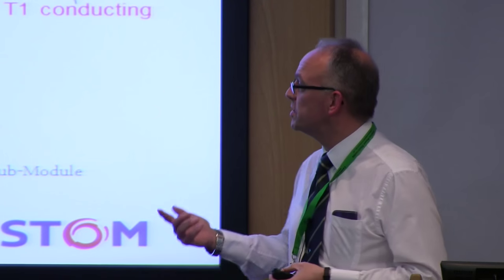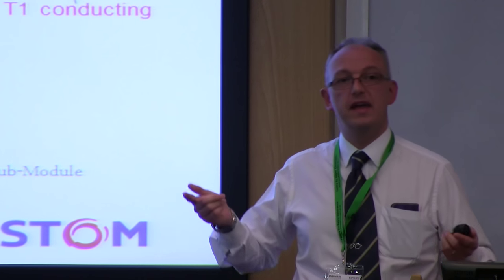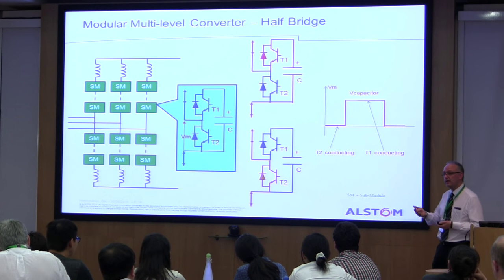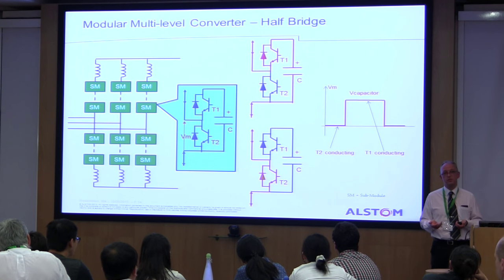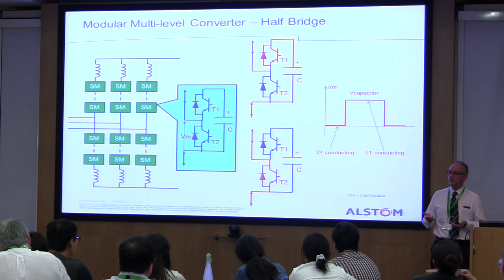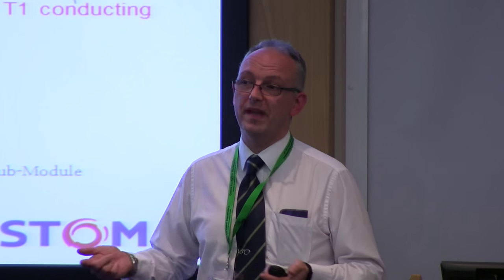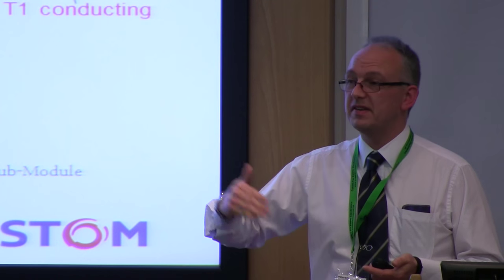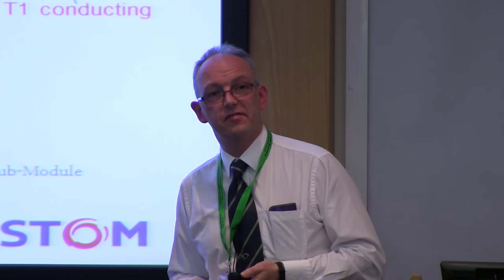To put 0.7% in perspective: for a 1000 MW converter, one percent is ten megawatts of loss at full power output. We typically have to meet capitalised losses — when we sell equipment, we sell it with capitalised loss guarantees. The customer assigns a price per kilowatt for every kilowatt of loss we declare, and that gets added to our selling price when evaluating offers. In Europe at the moment we're talking between 3,000 and 5,000 euros per kilowatt as the evaluated cost of losses.